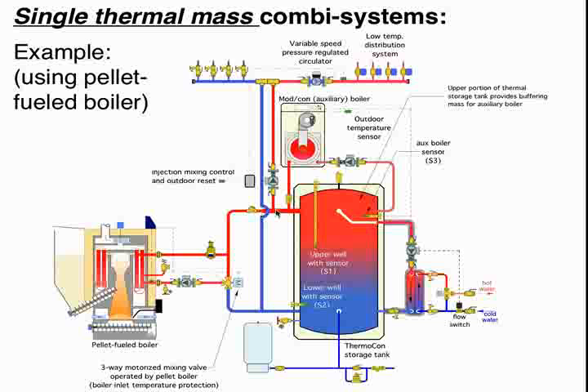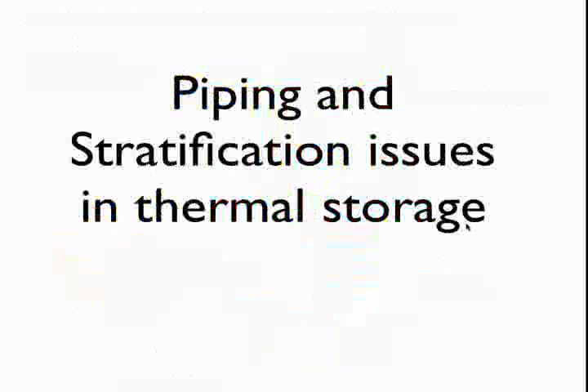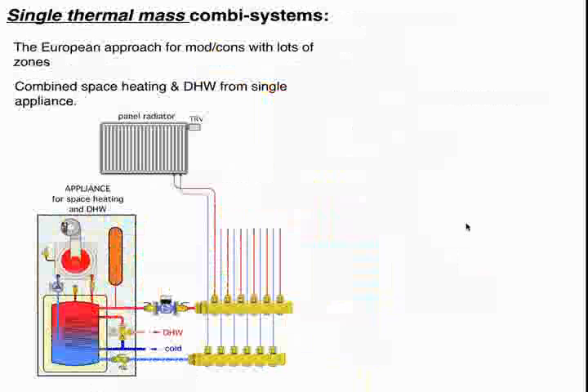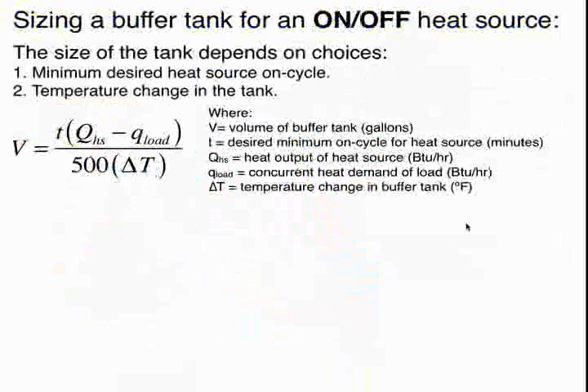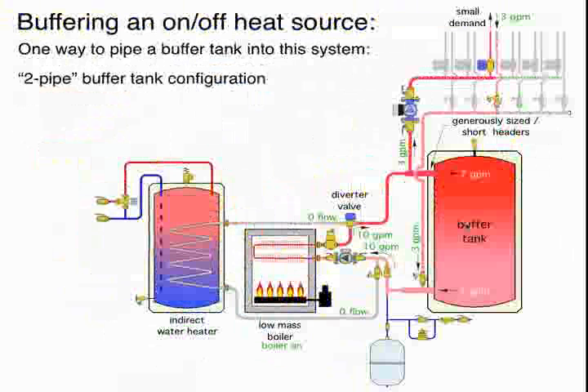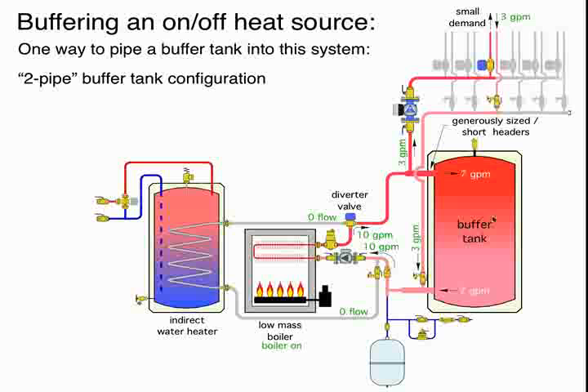John, you might want to go up to that schematic that had the buffer tank with domestic hot water on priority, and then you had a highly zoned system. I think you might have used both a 2-pipe and a 4-pipe arrangement as options. It might have been early. Yeah. Here it is with a 2-pipe. Oh, okay. Yeah, I guess it's that one. So if you're not on priority with your hot water and simply treating your domestic hot water as another zone, would you consider placing your buffer tank in a different spot in that design?